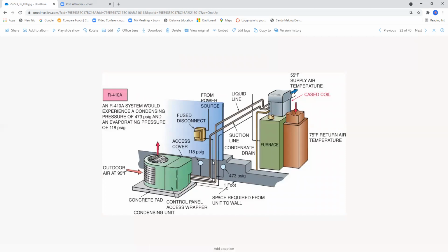And then basically our pressures are measured on the liquid line as well as the suction line. Because it's R410A, look what we're operating at on the low side: 118 PSIG, and 473 PSIG on the discharge side. You have your electrical disconnect, and basically this is normal. On a 95-degree day, these are the pressures we would expect to see at the condensing unit.